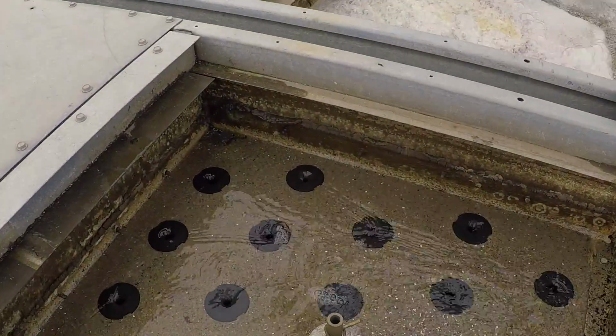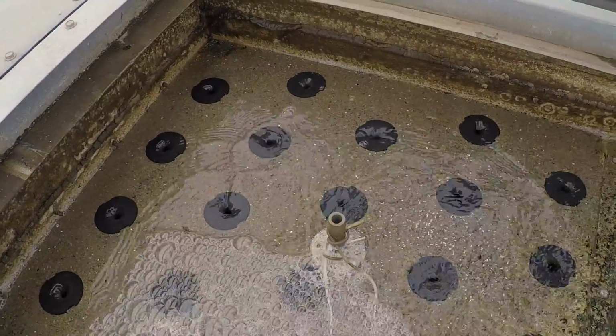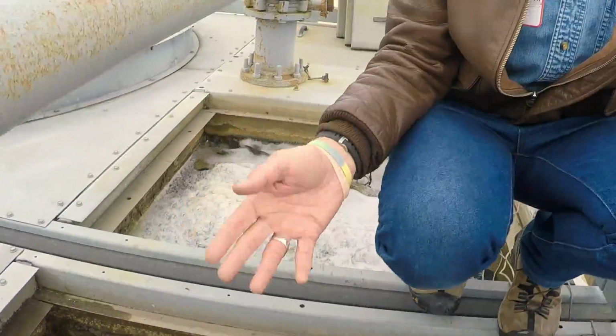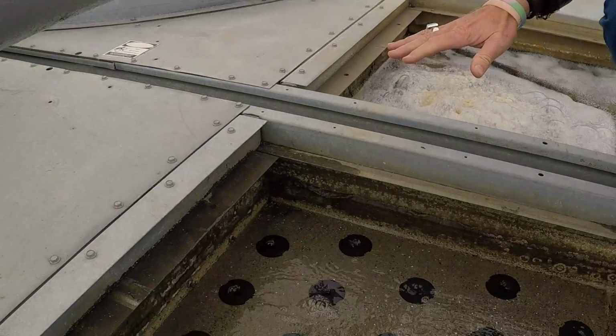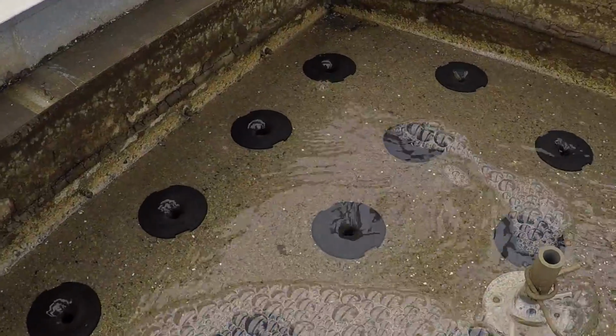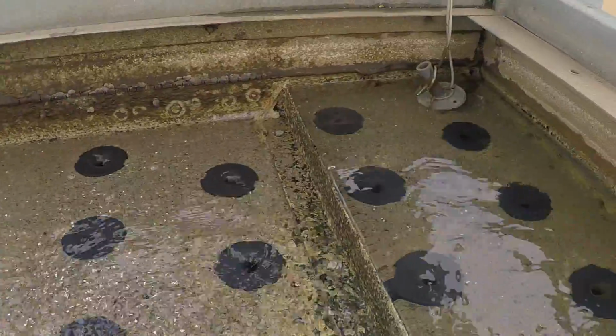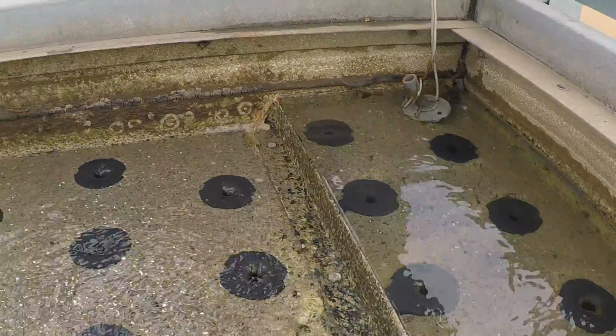Tower manufacturers have tables. They're curves, little log curves. The curves basically say for a given orifice size with so many inches of water, you get so many gallons per minute per nozzle, okay? So a couple things about that.